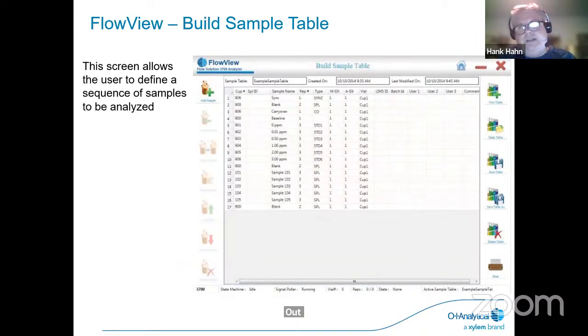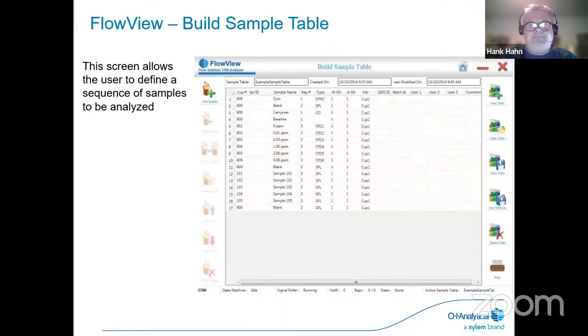You can also set up a wash after a run if you think you might have a really nasty sample, to prevent any kind of carryover or anything along those lines. And at the end of the run, you can also set up a wash as well. And this is again building the sample table.